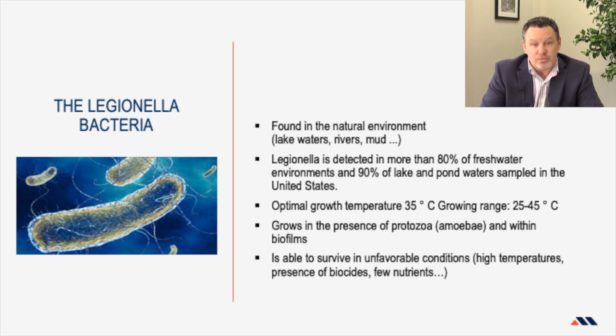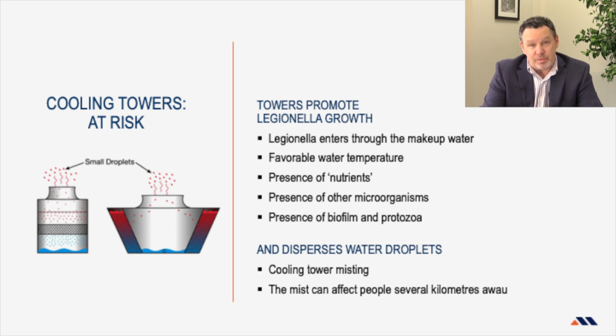Something to note is that where it really proliferates a lot in cooling towers, it likes to be around other microorganisms. If there are protozoa, amoebas, or algae, that's when you can get high concentrations of Legionella. So when we're trying to attack the microbiological activity in the cooling systems, we're not specifically going after Legionella only, we're going after the whole flora, but we are able to measure Legionella directly.